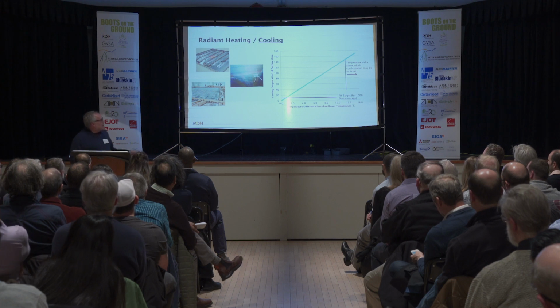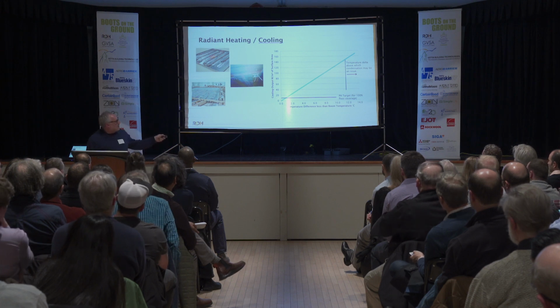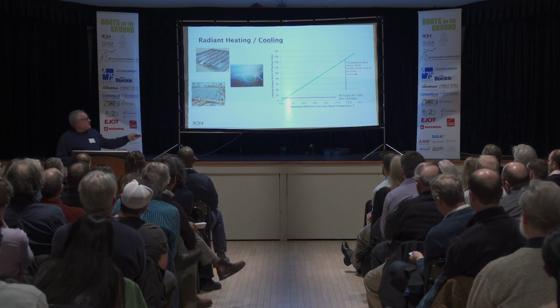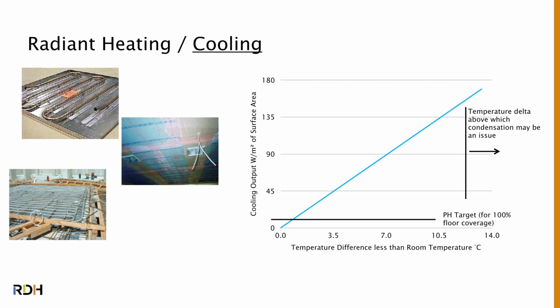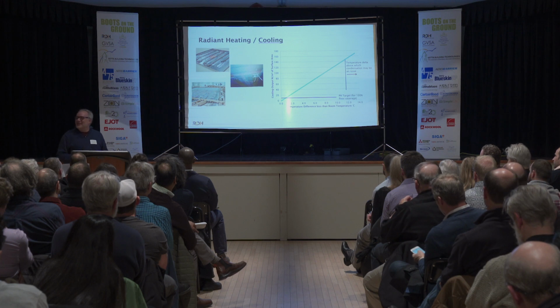Radiant cooling, kind of the same idea. Again, this is the type of output you get from a radiant surface, whether it's the floor or a ceiling. It tends to be closer to the same with cooling. And, excuse me, kind of a range we'd be targeting for passive houses around here. But if you push that delta, now you're talking a floor that's getting close to 15 Celsius. One, it's super uncomfortable, and two, you're at risk of creating slippery stuff.